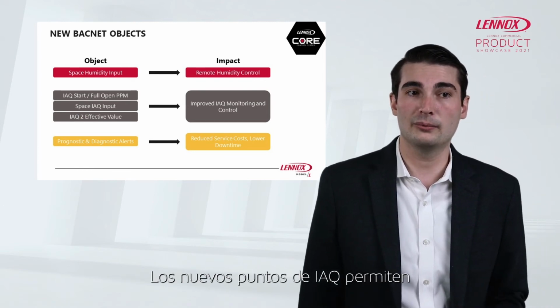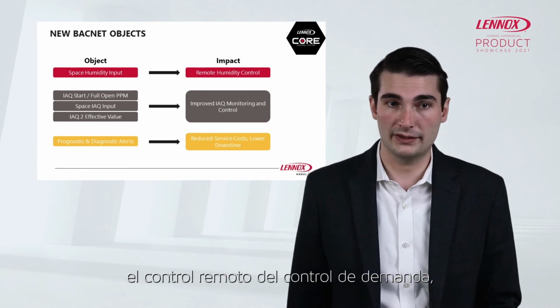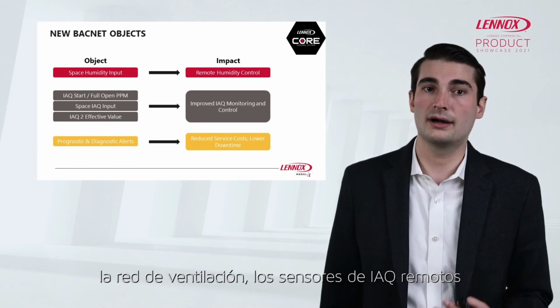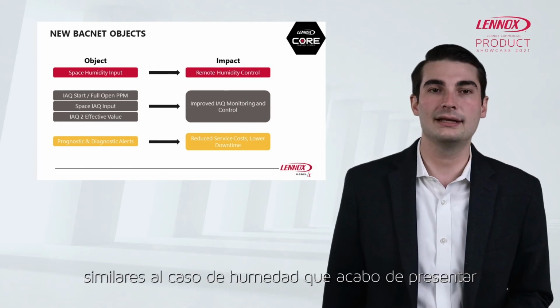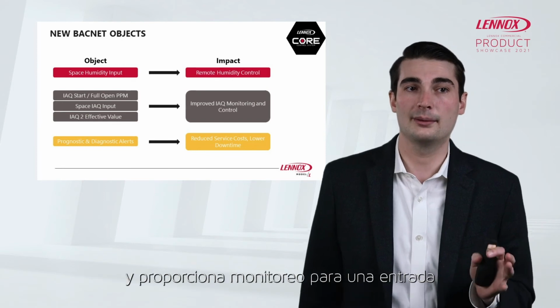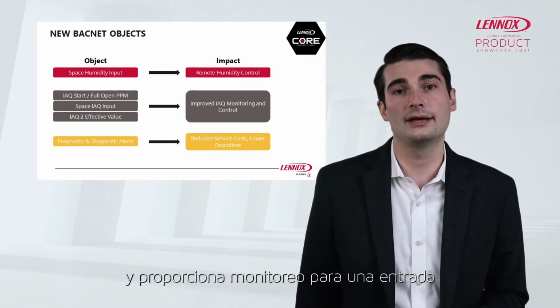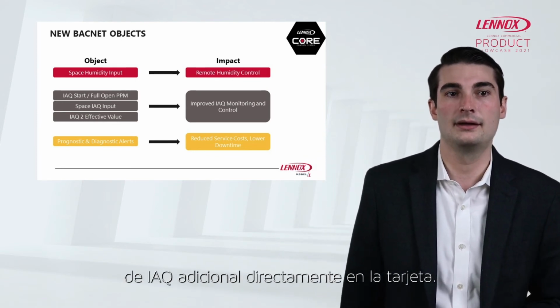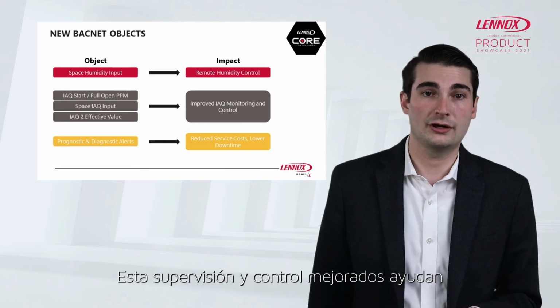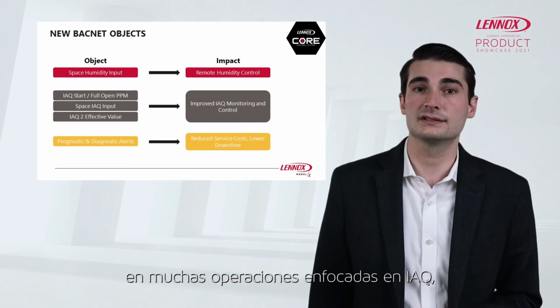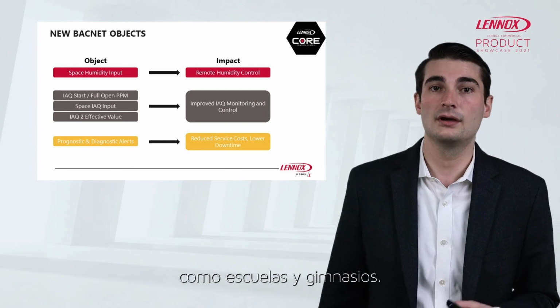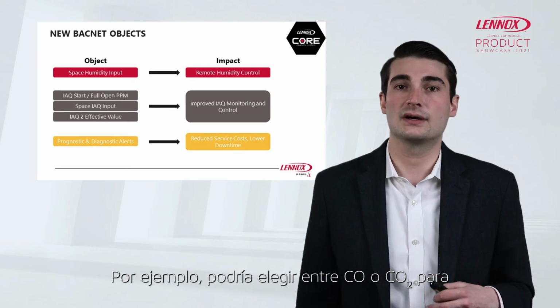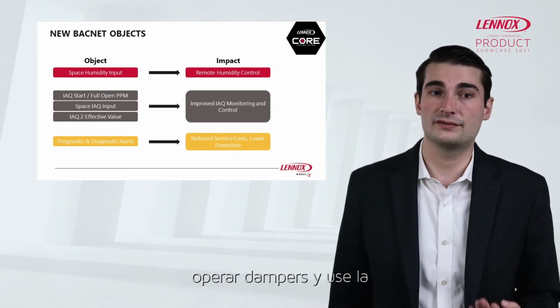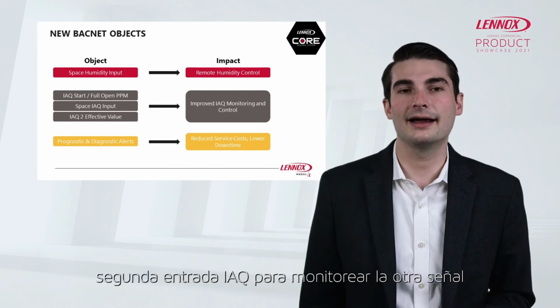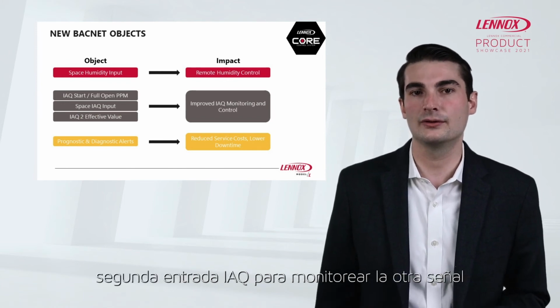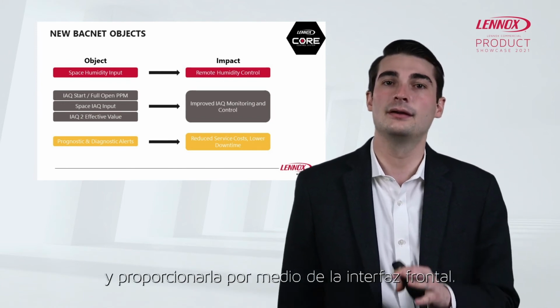The new IAQ points allow remote control of demand control ventilation, network remote IAQ sensors similar to the humidity case, and provide monitoring for an additional IAQ input directly on the board. This improved monitoring and control should help in many IAQ-focused operations such as schools and gyms. For example, I could choose either CO or CO2 to drive damper operation, and use the second IAQ input to monitor the other signal and provide that through the front end.